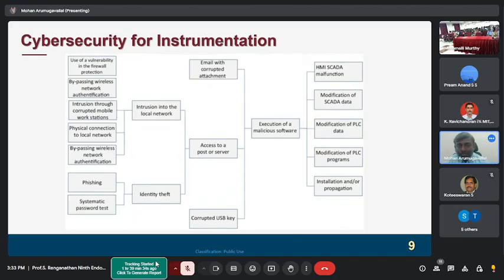In control systems we have controllers, a PLC, SCADA, or DCS. If you can manipulate the set point of a process, for example a sulfur removal unit, sulfur has to be removed but kept at a certain temperature so it flows out of the stream. If a hacker comes into the system and changes the set point or closes the valve for the temperature control, the sulfur solidifies in the pipeline, leading to breakdown, leakage, and loss of containment. It's a safety hazard and also an environmental hazard.